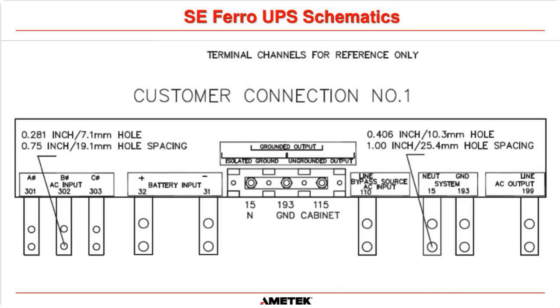Okay. And then the final connection would be your bypass. Now, the bypass and the AC output share the neutral. So you would connect your line or live output to terminal 110, and then you would connect your neutral out on wire 15. And once again, if you're running 3 wires out to the bypass, then with a ground, then you would connect the ground there. So if you have your load ground connected there, you would connect your ground to your bypass on that second hole there. Okay, and obviously we give you the size of our holes and the hole spacing and all that kind of good stuff there as well.